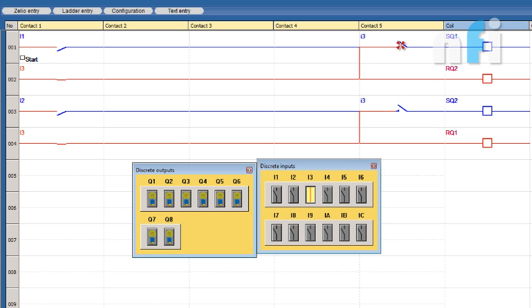That's why I have to take NC here and NO here, so that it should only affect the reset coils of both the outputs. That's the reason I have to use I3 here and take NC contact here to avoid its effect on SQ1 and SQ2. Okay, so this was interlocking using set reset command.